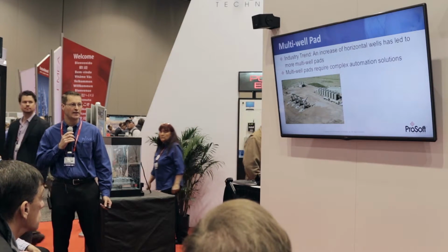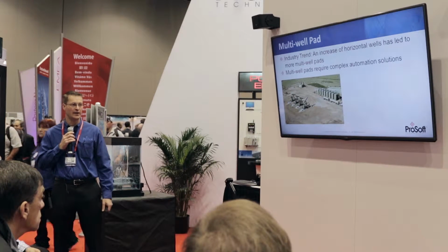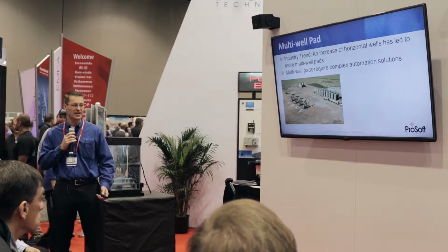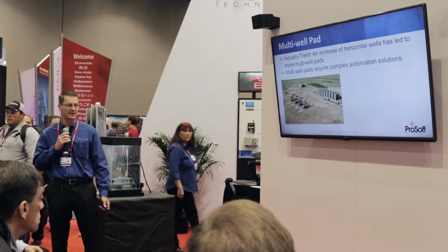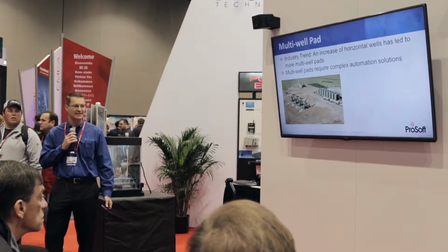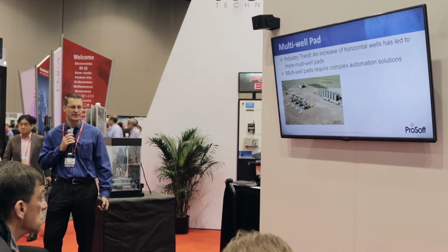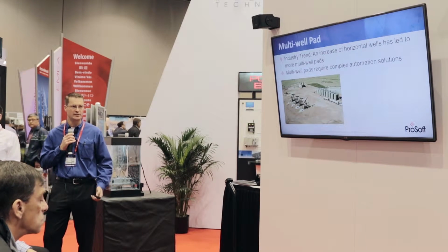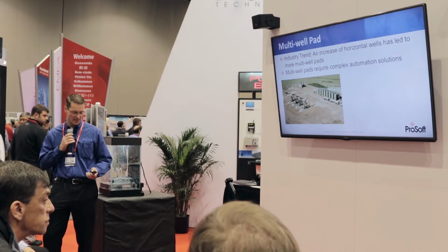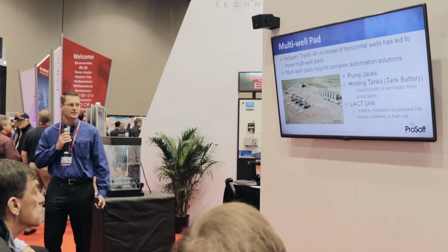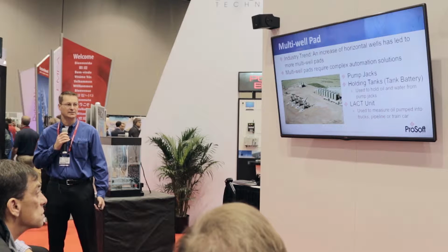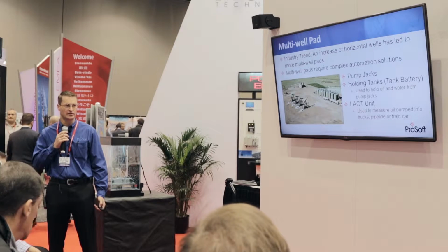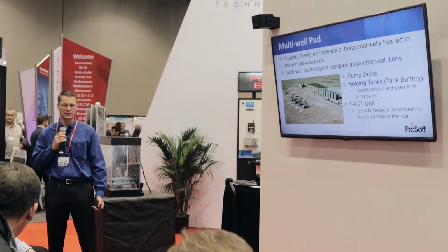And then you're bringing in multiple well pad sites, and these are becoming more and more complex systems. You've got tank batteries, vapor recovery units, three-phase separation on your well pad site. So it's extending beyond just traditional single well control, where you'd have a single hole in the ground and bring up a small RTU right there. So it causes the I/O counts to increase. Like we said, pump jacks, holding tanks. A lot of times you've got a LACT system on these locations, and a LACT system is used to measure the oil pumped into the trucks and pipeline.